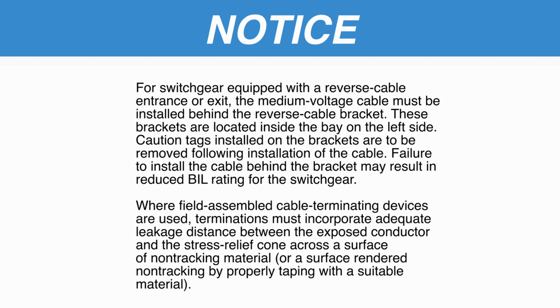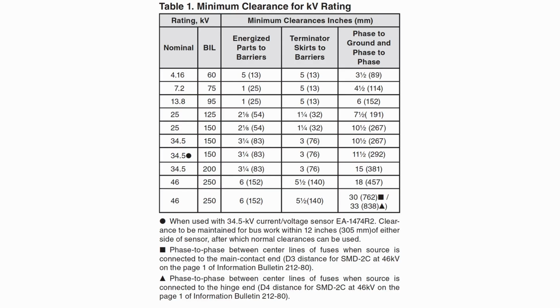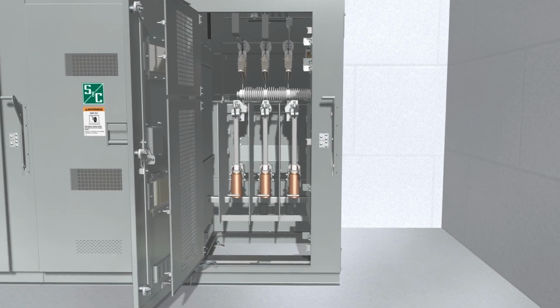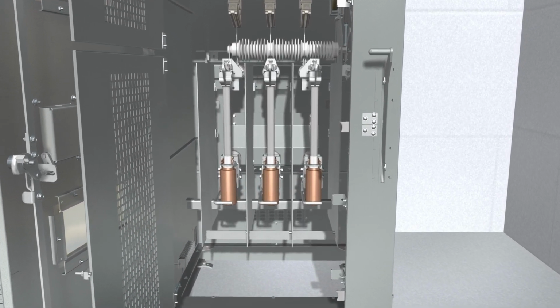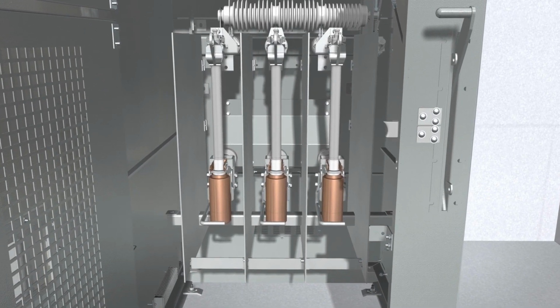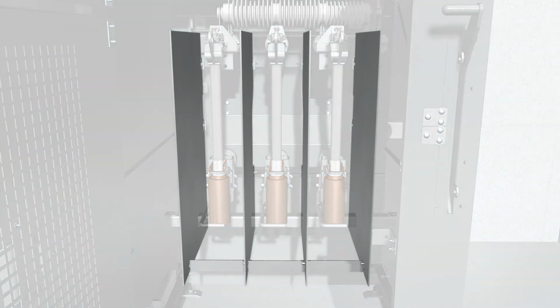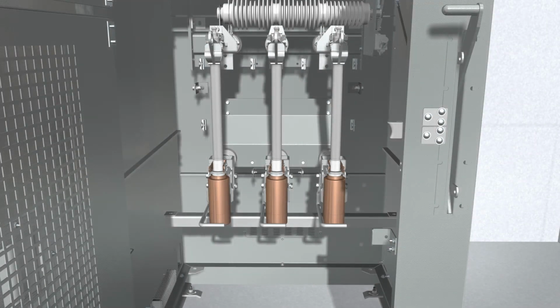Where field-assembled cable terminating devices are used, terminations must incorporate adequate leakage distance between the exposed conductor and the stress relief cone across a surface of non-tracking material, or a surface rendered non-tracking by properly taping with a suitable material. To maintain the rated BIL capability of the switchgear, the following minimum clearances from energized parts, including unshielded portions of cable such as terminator skirts, are required. If necessary, interphase barriers can be removed to facilitate makeup and connection of cable terminations to the switch, fuse, or bus terminals. If the interphase insulating barriers are removed, note their position to ensure correct reinstallation later.